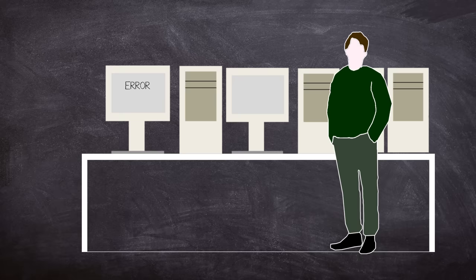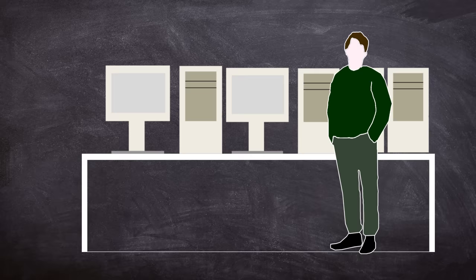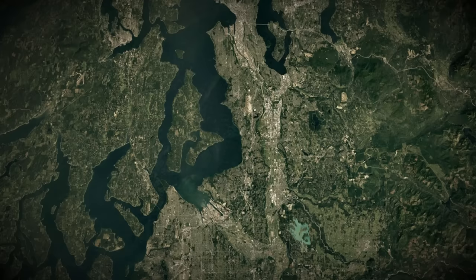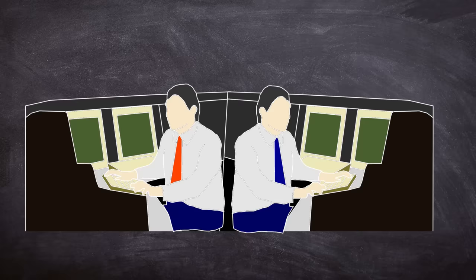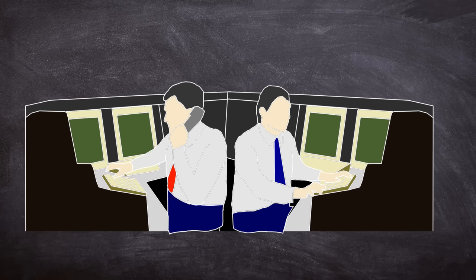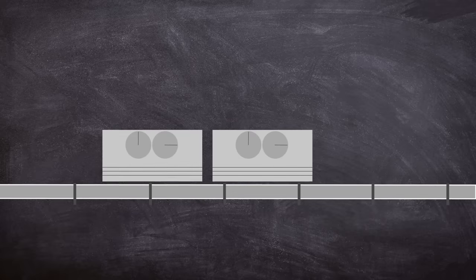At around 3:10 PM, the administrator began to note errors being logged on the SCADA system after undertaking database development work. At around the same time, one of the controllers began preparing to stop product delivery to the Tosco facility and start delivery of gasoline to the Harbour Island terminal in Seattle. At around 20 past three, the North controller contacted personnel at Cherry Point refinery and asked them to begin transferring product to the adjacent Cherry Point pumping station. The pressure in the pipeline began to rise.